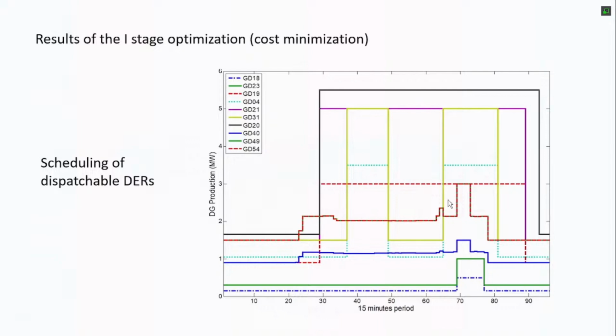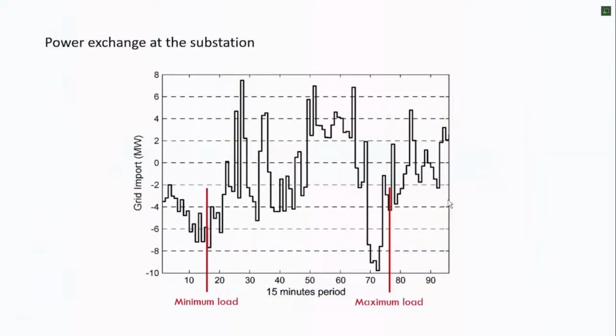You see that there are periods with very big production, and this justifies the grid flow during the day from the day-ahead dispatch. This is the profile expected for the power at the main substation. When it is negative, the production is above the consumption, so we expect to have a problem of too high voltage.